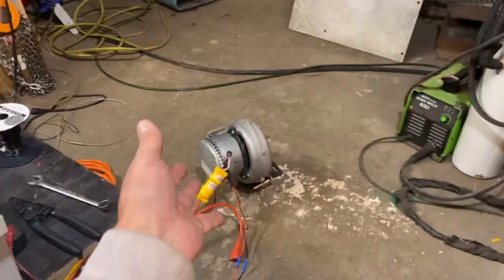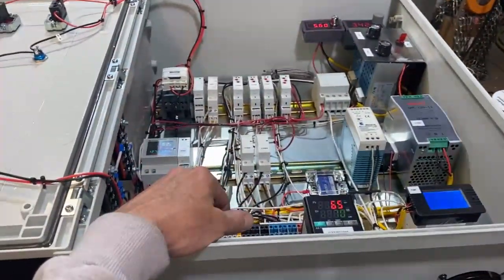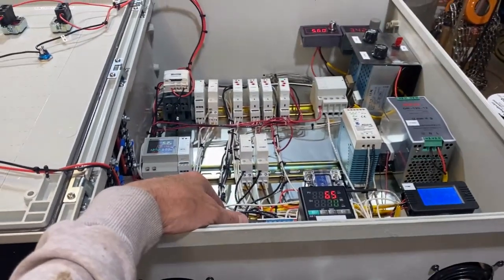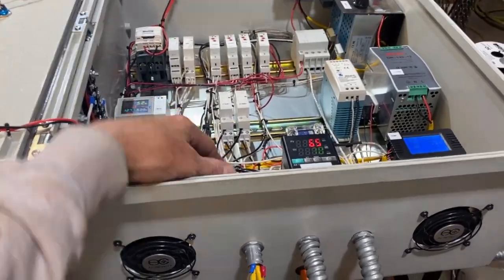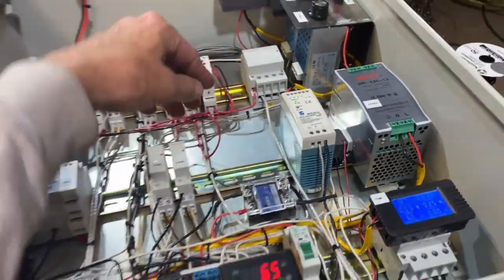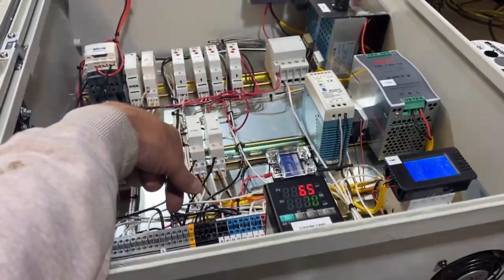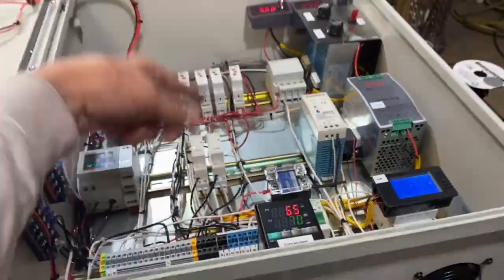The blower ran and then it cycled and went into a perpetual loop and it kept triggering this contactor and starting the timer all over again.